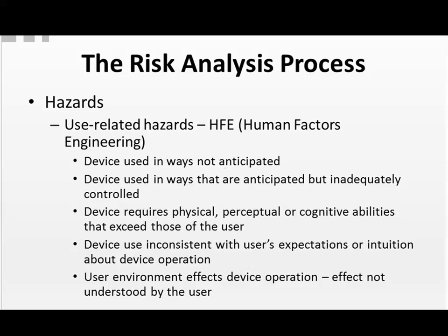Is the device use inconsistent with users' expectations or intuition about device operation? And does the user environment affect device operation, the effect not understood by the user? Are they using it in an area that's too high in humidity if the device is humidity sensitive, for example?